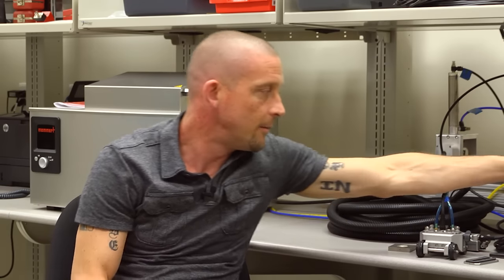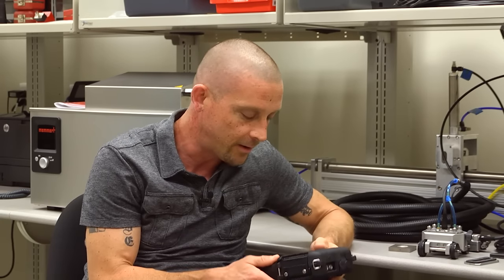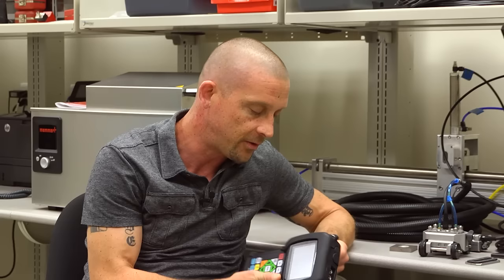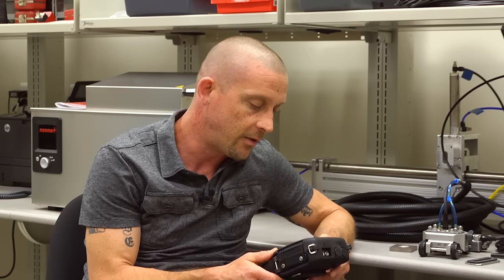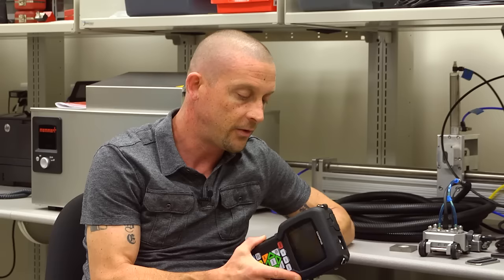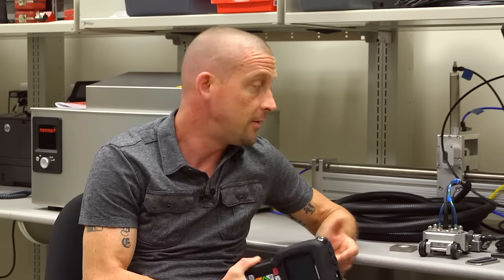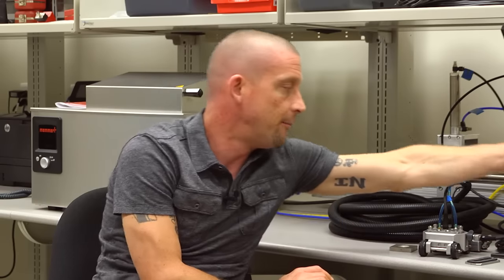Well, most of our customer base is doing one of two things. We have the 38DL Plus, which you're very familiar with here. It's been one of our long-standing gauges for providing thickness measurements to our customers. This is usually done as either a single point measurement or multiple point measurements. We can data log them into a database and use that data for remaining wall loss. Then on the high end of the market, what they've typically been used to is very rapid, fully automated scanners connected to a PC-based corrosion mapping system.